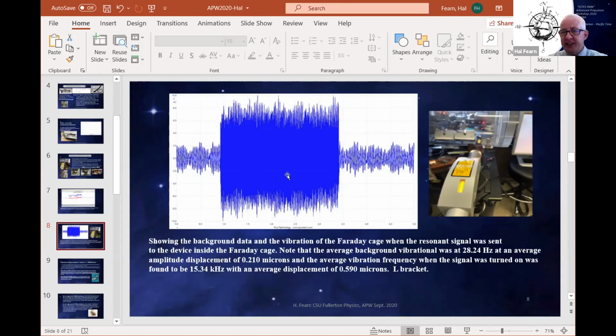And then when I turned on the resonant frequency of 35 kilohertz, again, this is directly on the Faraday cage without any vibration isolation, I found a frequency of about 15 kilohertz. So it's lower. The resonant frequency was 35 kilohertz. This was 15 kilohertz with a displacement of about 0.6 microns. So it's not an awful lot. And that's using the L bracket. So that was with the L bracket.